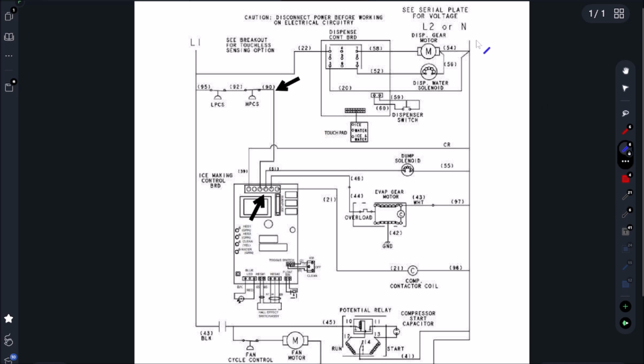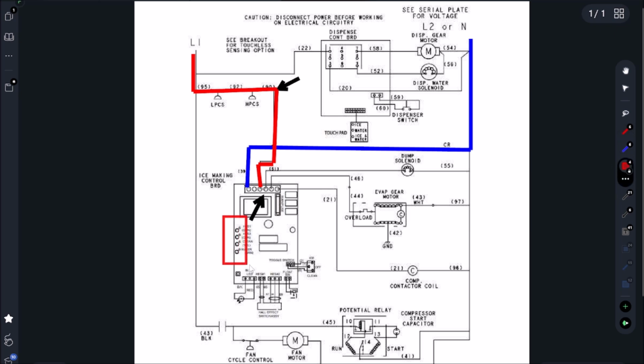So let's just draw out our schematic here. So our board's getting power from 39. That's just a straight shot from a neutral. We're good on there. Okay, we're losing power somewhere on this line here because we didn't have power at 90. And that's why we didn't have any LEDs on the board right here. That means we're dropping power through either our high pressure cutout switch or our low pressure cutout switch.